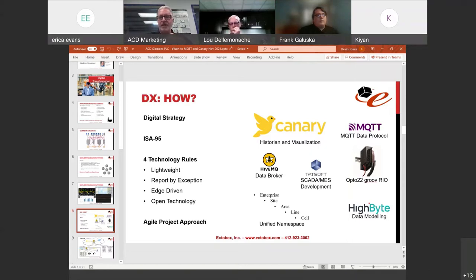Publishing data in one direction helps with less bandwidth — you're not doing the poll-response thing. Also, data goes in the right direction: with poll-response, if there's a firewall in between, you have to open up holes in that firewall to allow the polling process to communicate through to the PLCs. If you're going in one direction only, you don't have to worry about poking holes in the firewall — it's more secure. Third, edge-driven: drive data and decisions from the edge process.